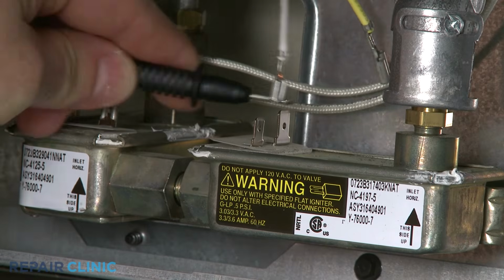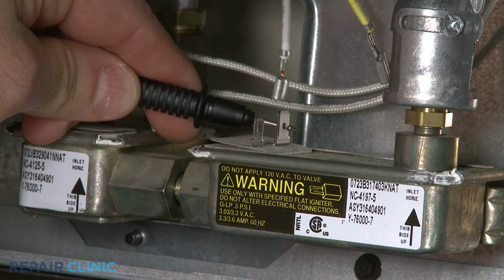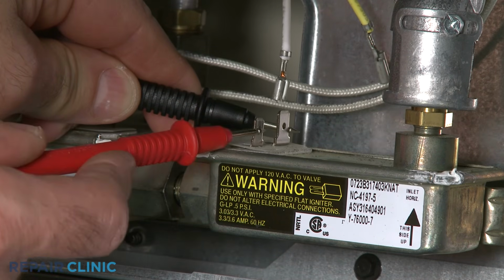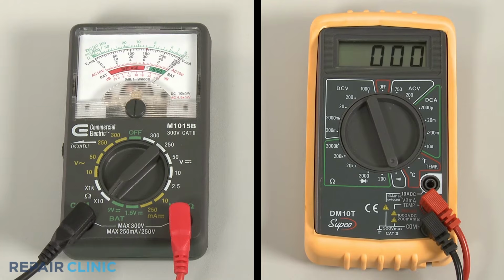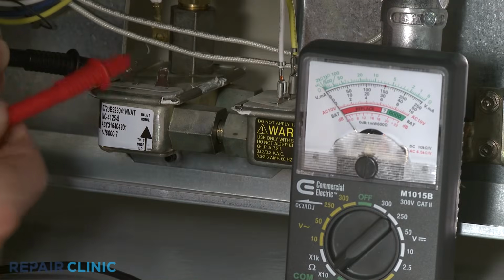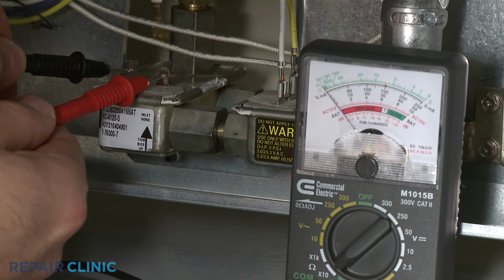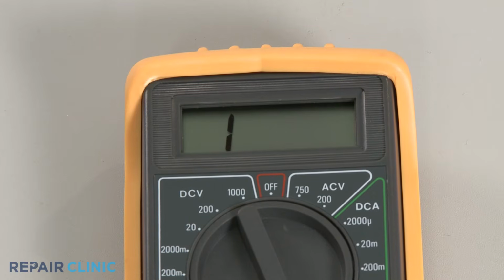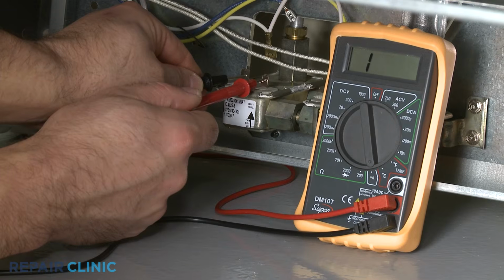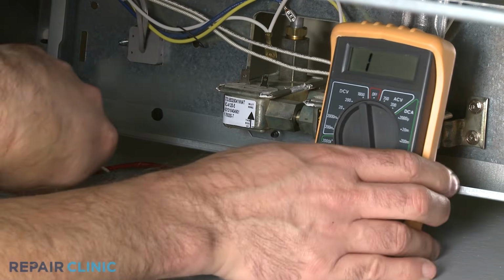Now, use a probe to touch one of the valve's terminals and the second probe to touch the other terminal. If the meter reading shows a result between 0 and 5 ohms of resistance, the valve has continuity and should be functioning properly. However, if the meter's needle does not move or the digital display does not change significantly, there is no continuity, which means the valve is defective and will need to be replaced.